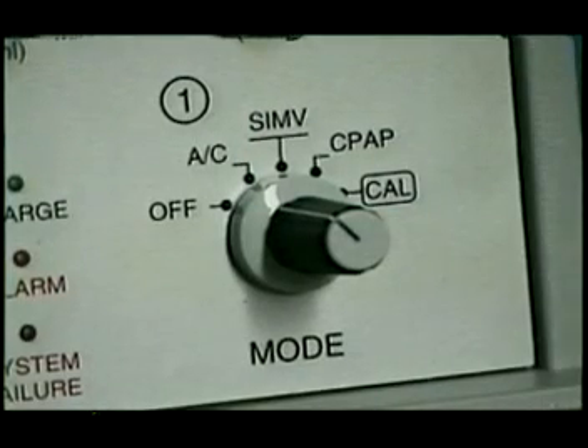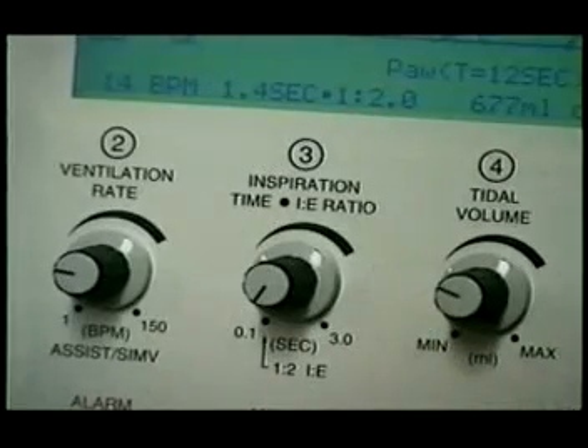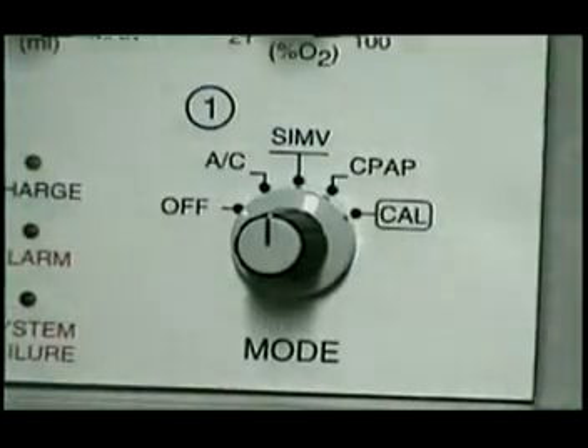Assist control delivers a combination of assisted and controlled breaths. The rate setting is a default setting that assures your patient will receive the minimum number of ventilator-generated breaths selected. If the patient is spontaneously breathing at a rate greater than the default setting, the ventilator will synchronize to each spontaneous effort and deliver a breath in accordance with the inspiration time and tidal volume control settings.